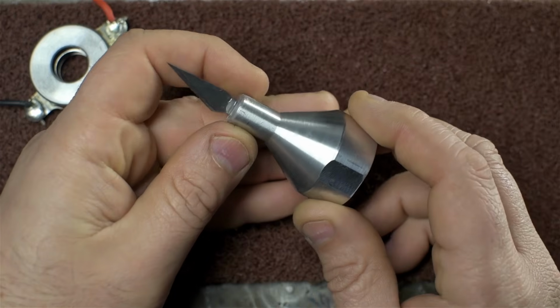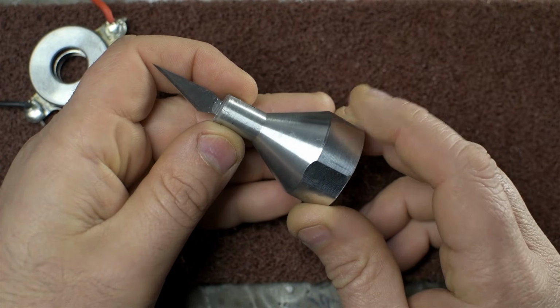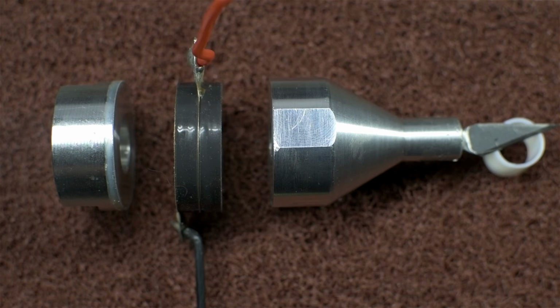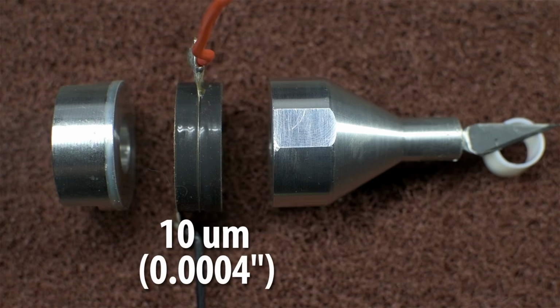Let's just talk a little bit about the end game as far as the horn is concerned. Talk about how this design came about. The vibration of the piezo, how much it moves when it gets excited, just on its own is very low. Somewhere maybe around the 10 micron mark. Maybe 8, 9, 10. That's about 4 10,000ths of an inch. If you weren't sure, that's not a lot. The horn hopefully serves to amplify that, magnifies it. Just like the horn on the megaphone, remember? A little bit of motion here, whole lot of motion here.